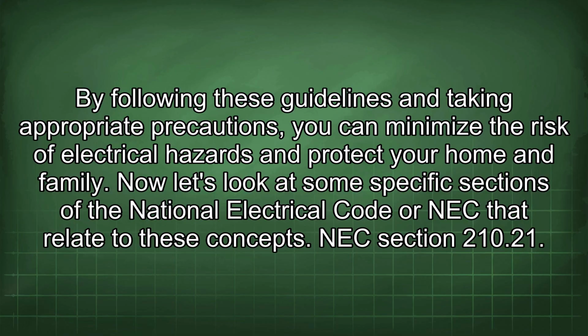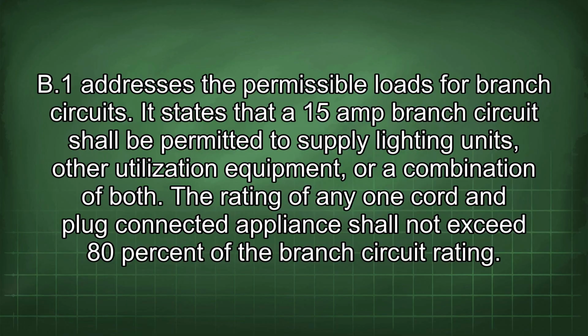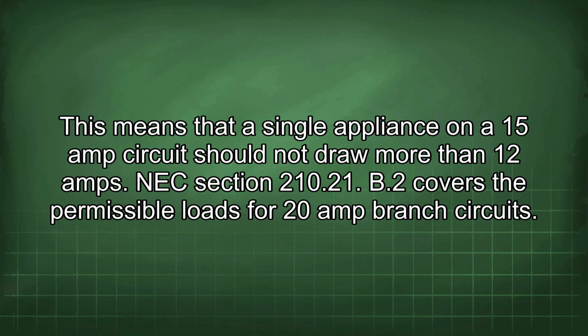Now let's look at some specific sections of the National Electrical Code, or NEC, that relate to these concepts. NEC Section 210.21(B)(1) addresses the permissible loads for branch circuits. It states that a 15 amp branch circuit shall be permitted to supply lighting units, other utilization equipment, or a combination of both. The rating of any one cord and plug connected appliance shall not exceed 80% of the branch circuit rating. This means that a single appliance on a 15 amp circuit should not draw more than 12 amps.